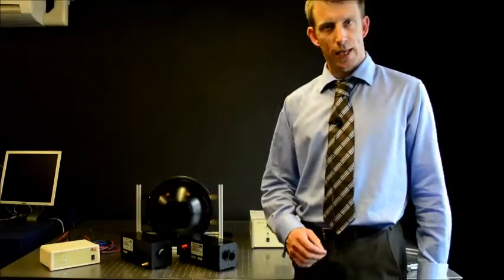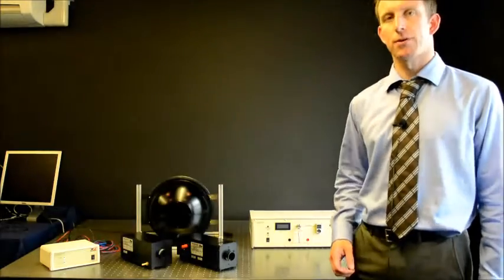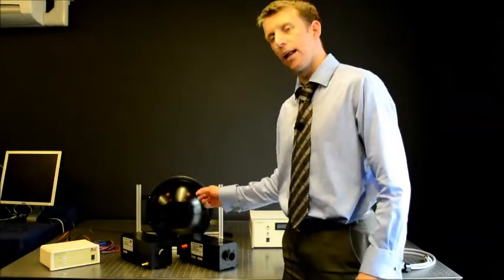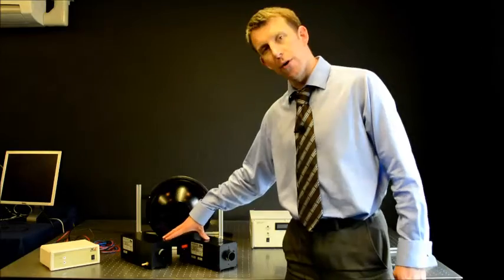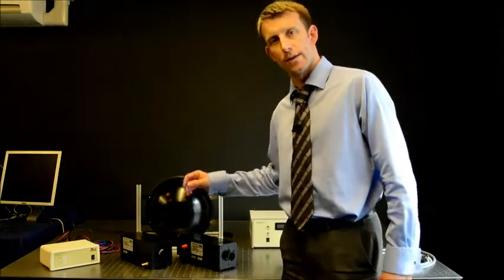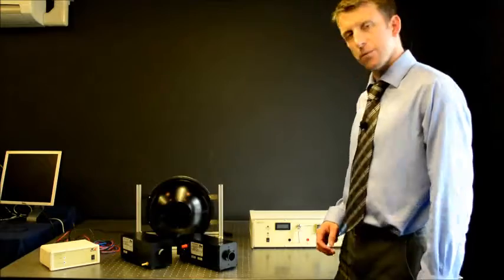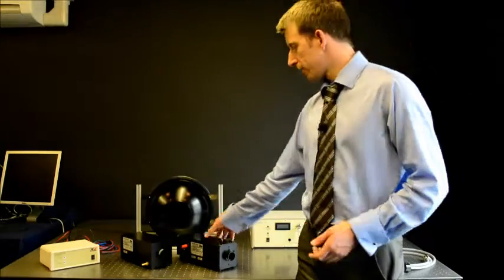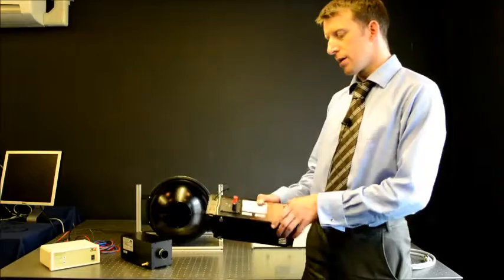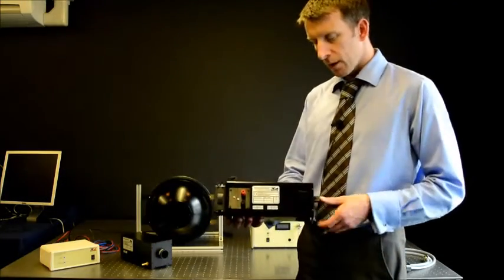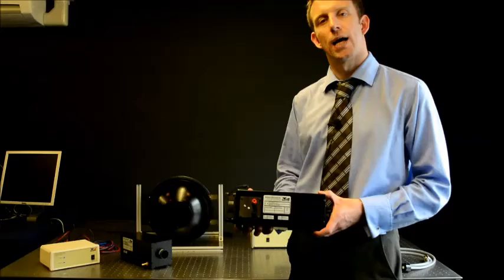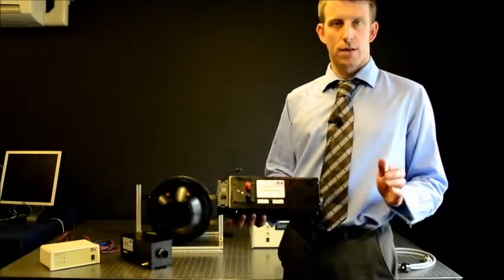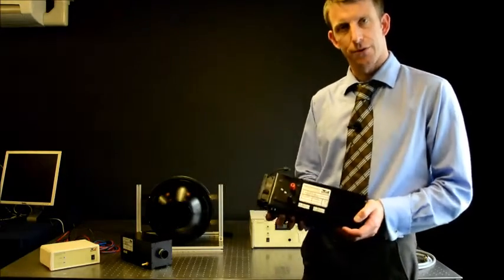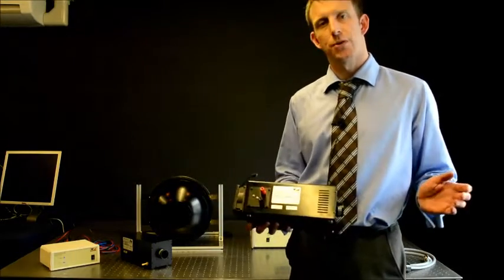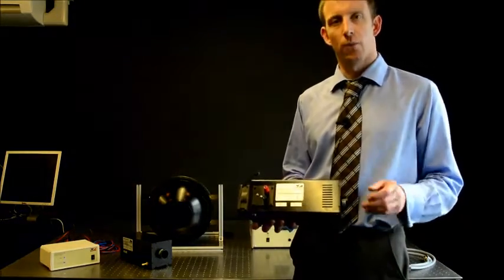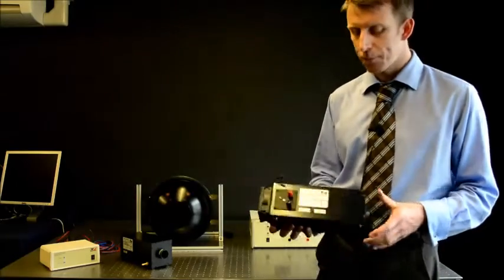For the purposes of system calibration in spectral irradiance and spectral radiance, we have 3 calibration standards: 2 irradiance standards and 1 radiance standard. In terms of the spectral irradiance calibration, we have first the CL6H quartz halogen based source. It's fitted with a 150 watt quartz halogen lamp, which provides spectral irradiance calibration from 300 to 3000 nanometers. Below 300 nanometers, the emission is very low and one has to use a second lamp.